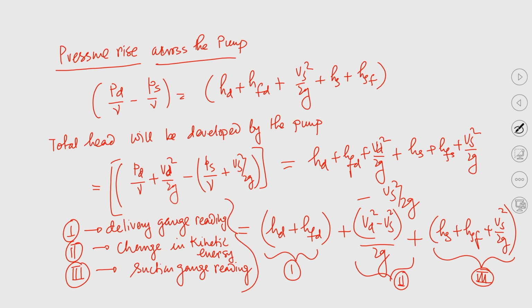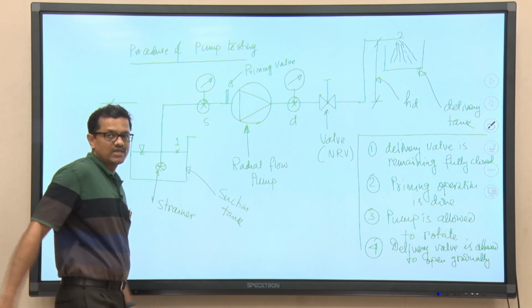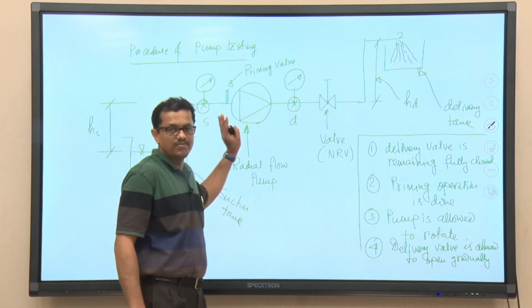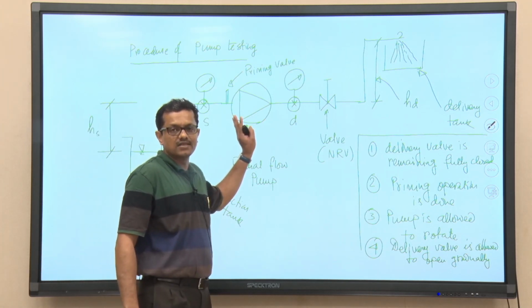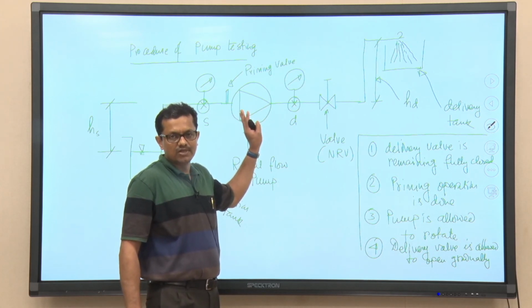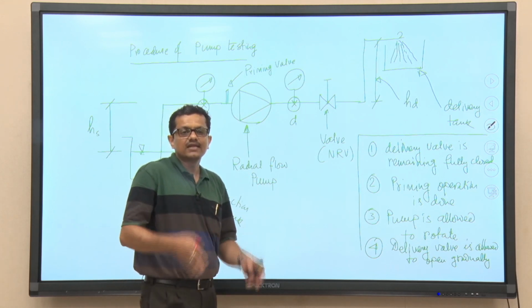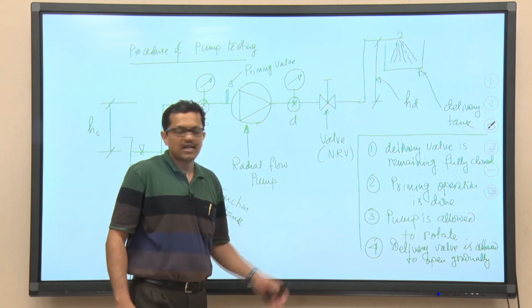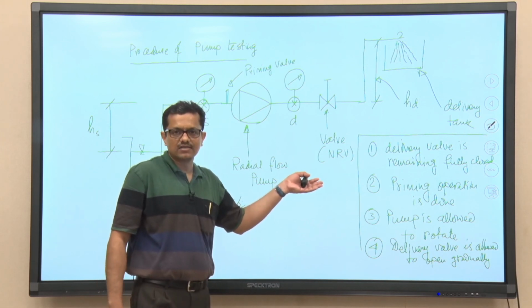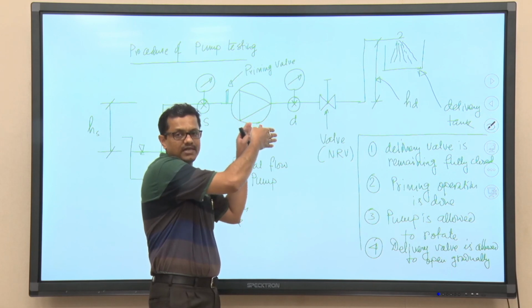So, essentially, you can understand from this pump testing circuit, we can measure the total head being developed by this pump. We also can measure the flow rate that is supplied by this pump by using the V notch or this pitot tube. So, from those data we can generate the H-Q curve, and the other two curves I have already discussed. Now, the question is, this is what we obtain at a given speed, right.